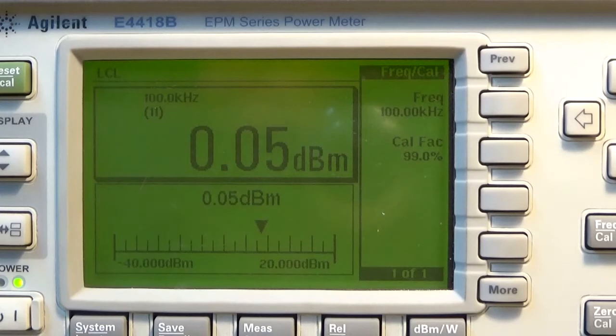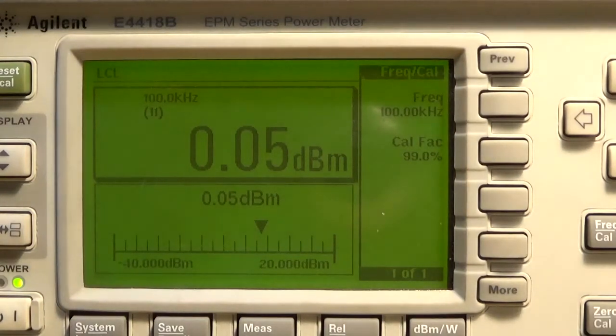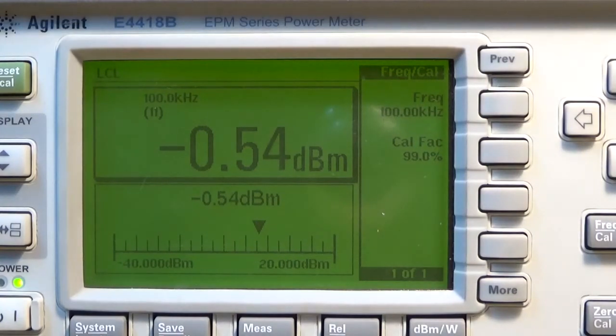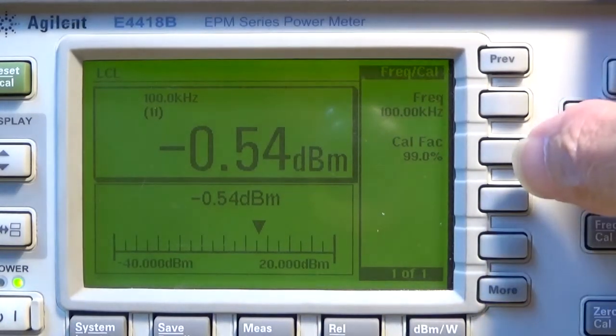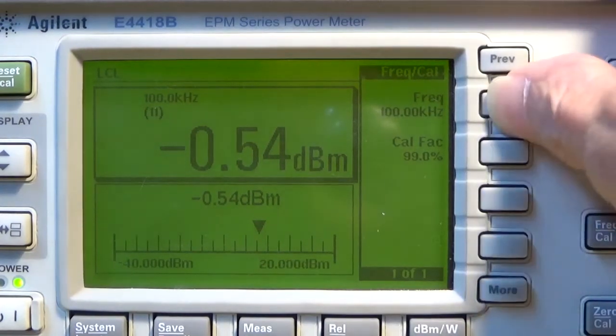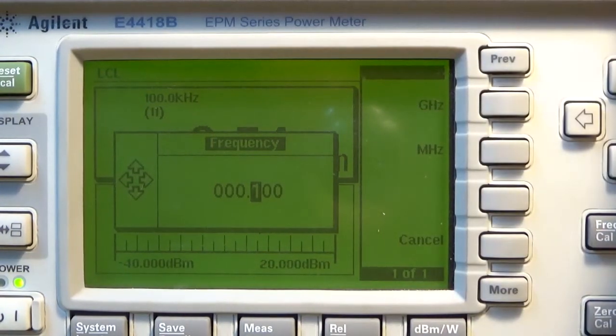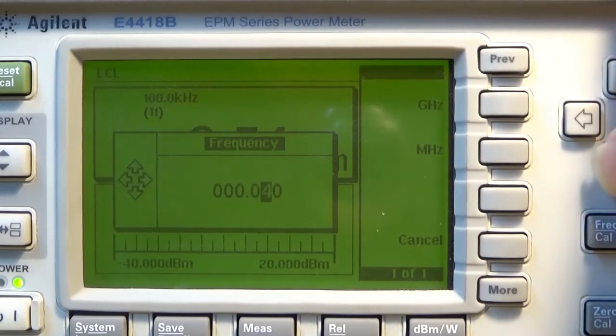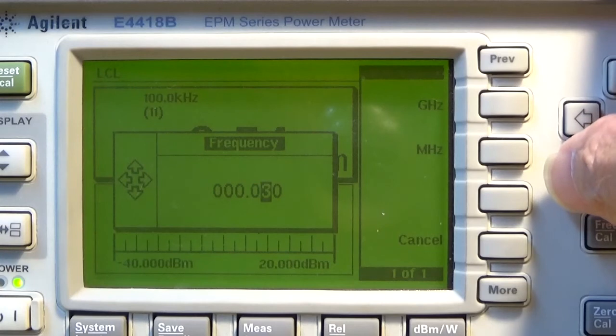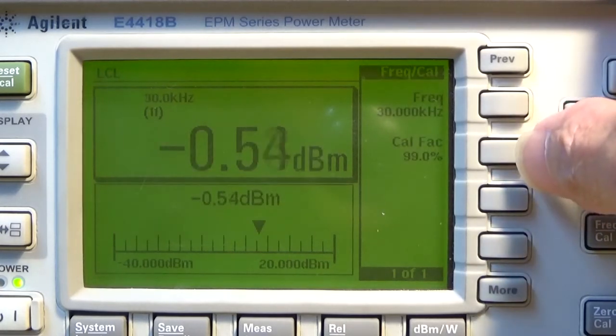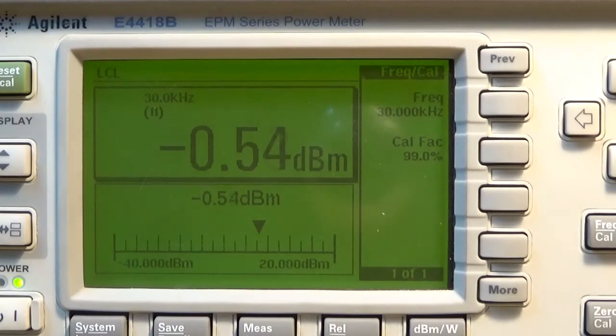Let's have a look and see how low I can go before I get some inaccuracy. So if I go below 100 kilohertz, which is what this sensor is rated at, no, it's 30 kilohertz, isn't it? Okay, let's take it down to 30. And it's starting to drop off a bit. So I'll change that really, shouldn't I, to 30 kilohertz. Okay, so I'm just going to assume that my generator drops off at 30 kilohertz.